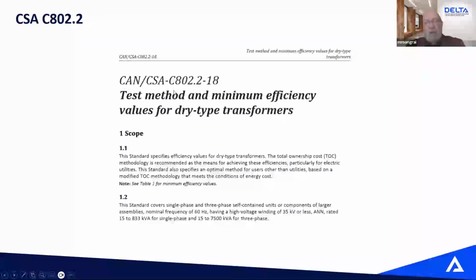So NRCan law, and then we have CSA C802.2, which is the test method for the efficiency of transformers, and the -18, that's the latest revision. So it was amended in 2018, and it was put in application by NRCan in 2019. So when you say NRCan 2019, it's just that in 2019, NRCan passed a law to comply with higher efficiency, but it's CSA C802.2-18, which contains those efficiencies and how we test them to be compliant with those efficiencies dictated by NRCan.